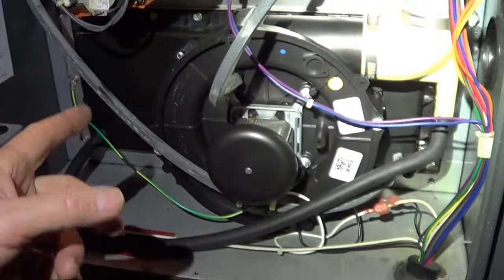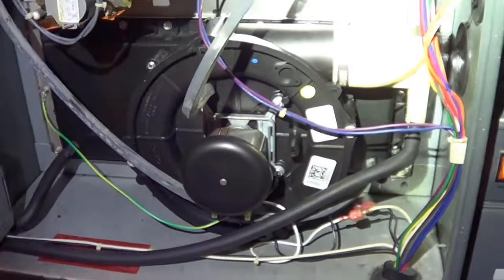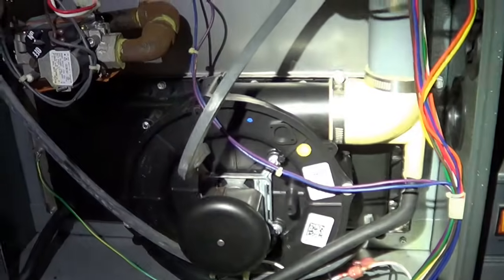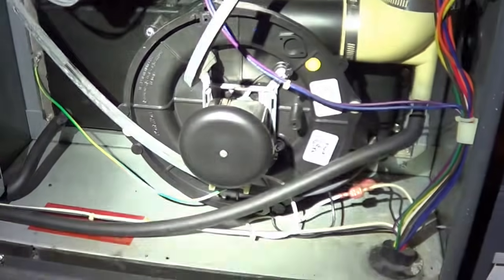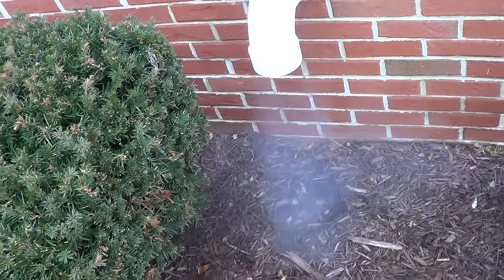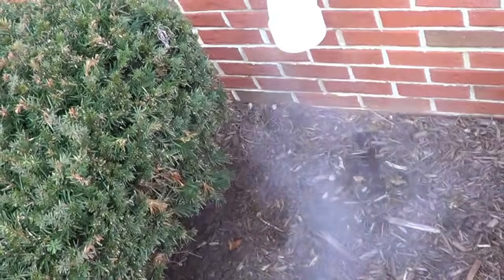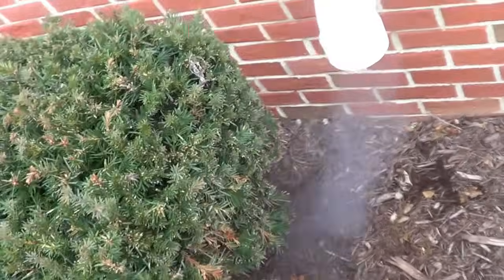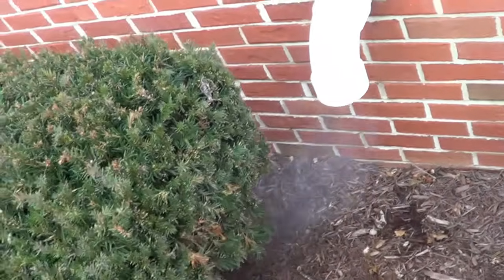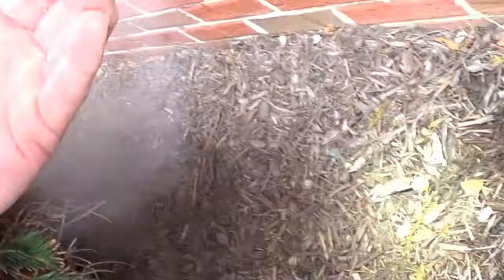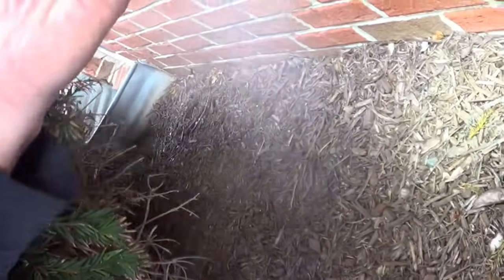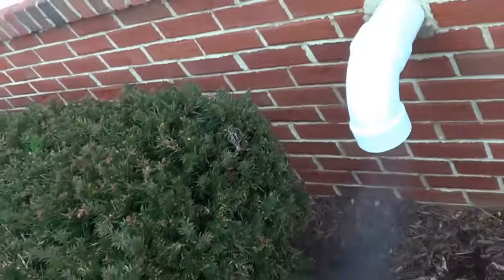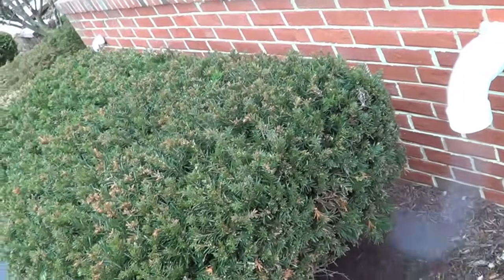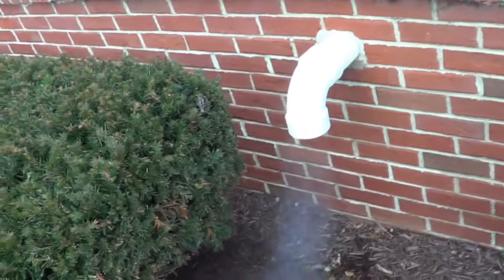So what's happening is the heat exchanger got clogged up because of the lack of enough oxygen. You're running too rich. On this furnace, the exhaust was starting to get stinky, and that's the clue that the heat exchanger is clogging up. Normally on the exhaust, it should have hardly any odor at all. Propane will have a slight propane smell, but this is natural gas, and it was actually smelling like a propane furnace.